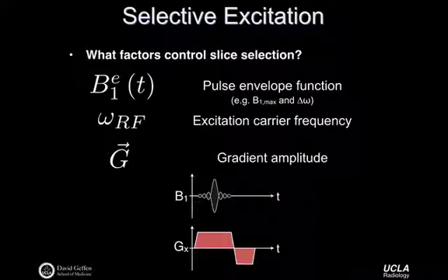What is the envelope function? Well, the envelope function changes the magnitude of the current as I'm oscillating. Am I oscillating a big current through, or a small current, and then a big current, and then a small current? Those sinc functions have an envelope that looks like a sinc function on it. That imparts a specific range of frequencies on your RF pulse. So that RF pulse that has a sinc-like envelope function will have a particular center frequency, as well as a very specific excitation bandwidth. The shape of that pulse is what governs the excitation bandwidth. But we just play it as one thing.